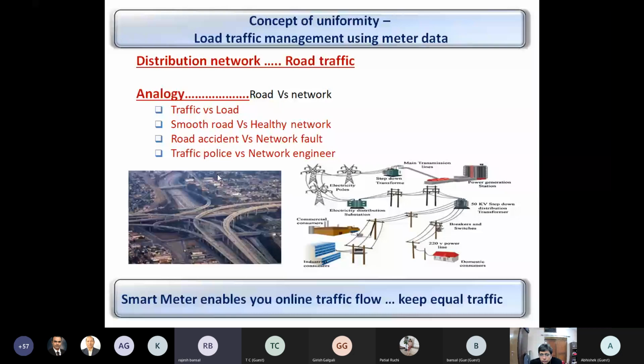The bell curve of the loading of assets, some were underloaded, some were overloaded. Now the bell curve has squeezed, and because of that, our technical loss has gone down, our failures have gone down, our faults have gone down, and definitely preventive maintenance has gone down, and so on, and the reliability has gone up. So this is how I want to bring smartness.